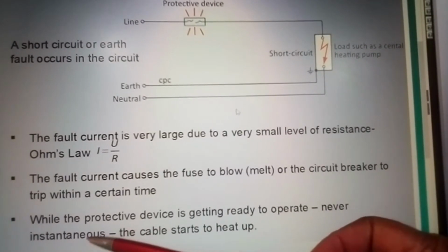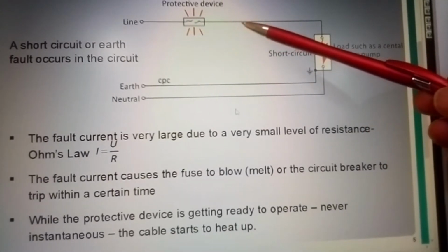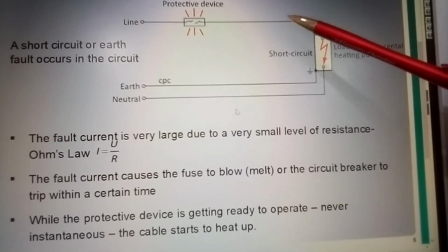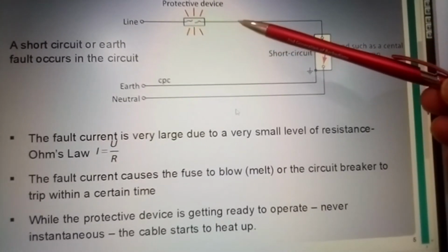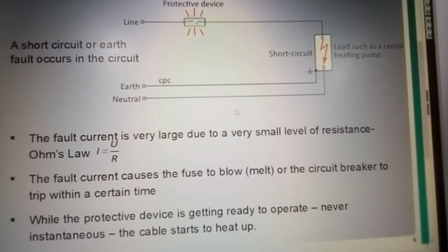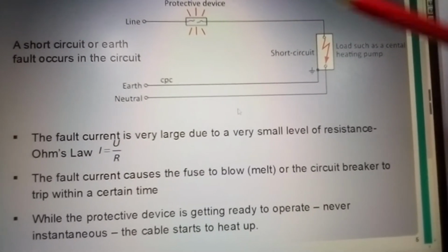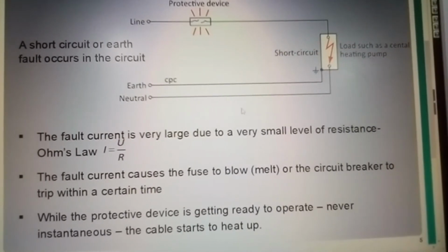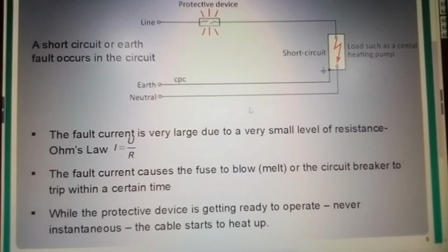The concern here is the length of time it takes for this fuse to melt, and the effect it may have on that cable to your load. It is the time it takes this fuse to blow that will determine the melting effect of the current going through the cable, thereby bringing about a large power surge. That is what we need to minimize, so that the cable can handle the current up to the time that the fuse will blow or the circuit breaker will trip.